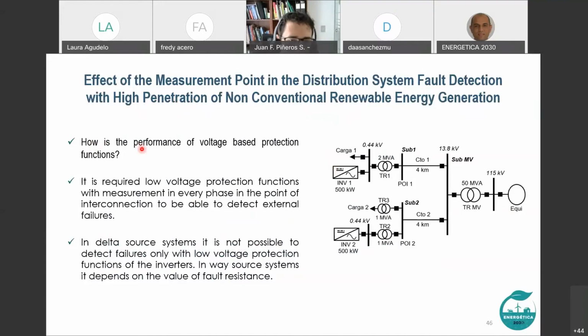How is the performance of voltage-based protection functions? And after the simulations, I will show you two main points we were having about this. We now think it's clear. It is required to have a low voltage protection function with measurement in every phase at the point of interconnection to be able to detect external failures.